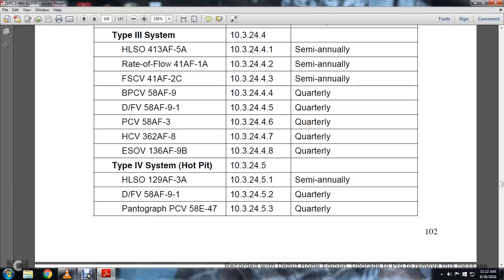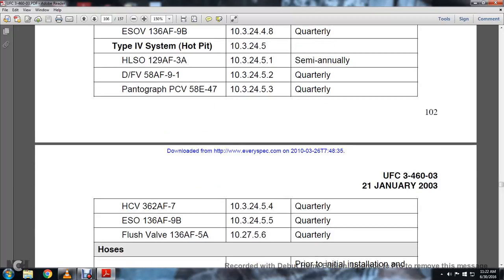Type 4 system, hot pit. The high level safety operation automatic valve, 129 AF 3A, 10.3.24.5.1, semi-annually. Defueling flush valve, 58 AF 91, 10.3.24.5.2, quarterly. The pantographic pressure control valve, 58E-47, 10.3.24.5.3, quarterly. The high control valve, 362 AF 7, 10.3.24.5.4, quarterly. The ESO valve, 136 AF 9B, 10.3.24.5.5, quarterly. Flush valve, 136 AF 5A, 10.3.24.5.6, quarterly.